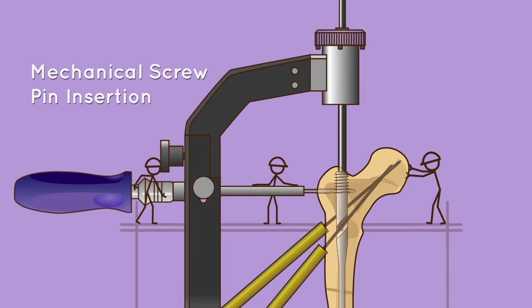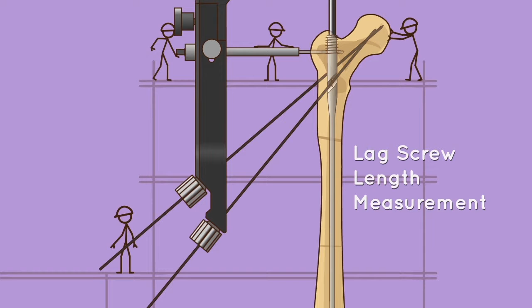Lag screw insertion: lag screw length measurement. Using the depth gauge ruler, measure the lag screw lengths. If the measurements fall between two markings, always select the smaller length. Remove the depth gauge ruler and depth gauge sleeves once measurements are obtained, leaving the depth gauge wires in place.